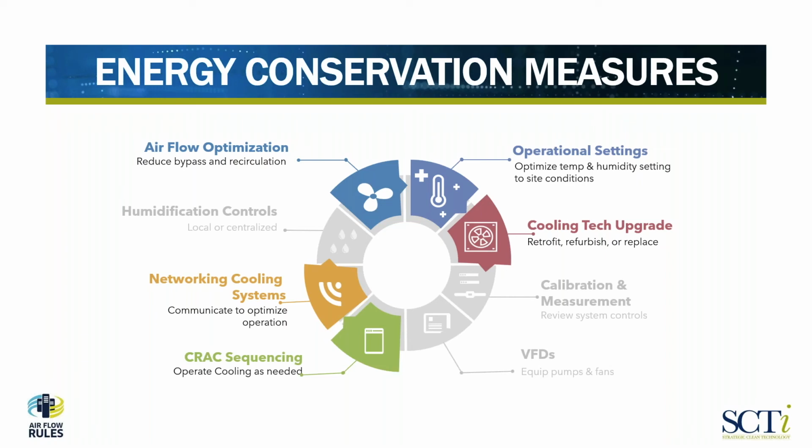But then once we've gone through and done the rest of the work that we've identified here, once we've used the rest of the tools out of our toolkit, the appropriate ones, we then go back and do airflow optimization, which means, given I've improved the management of the air, given I've improved the temperature, how much can I dial down the airflow in that site and optimize the amount of air that's being delivered to the IT equipment.